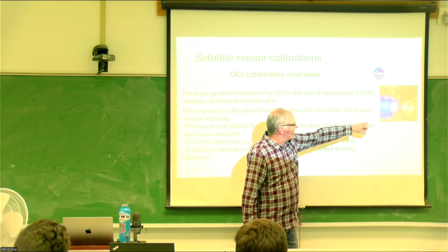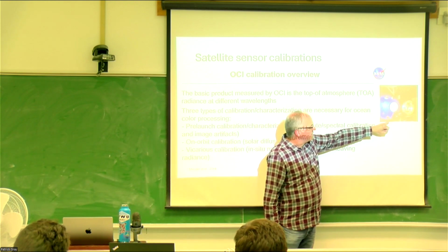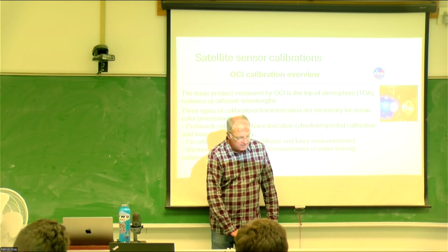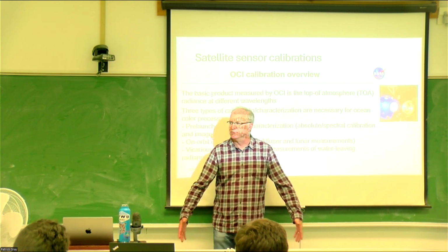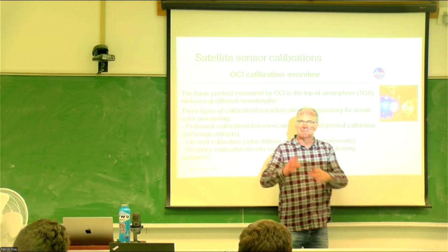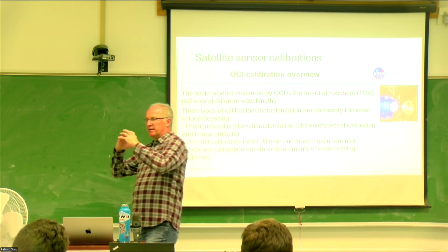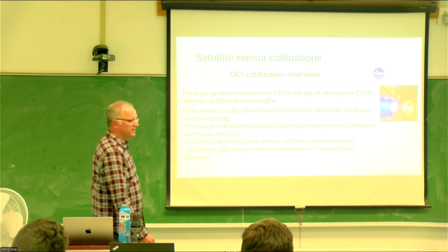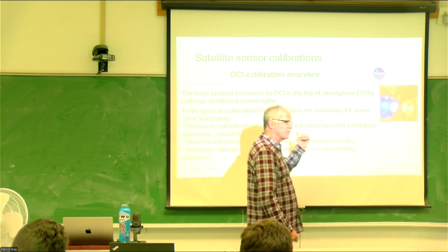But here it's integrated. For context, you can't really see it, but that integrating sphere is about that tall. It's a huge one. That's because you need to open this aperture enough to fit the rotating optics in the plane of view of that output, because it's much bigger optics than what we use in the field.